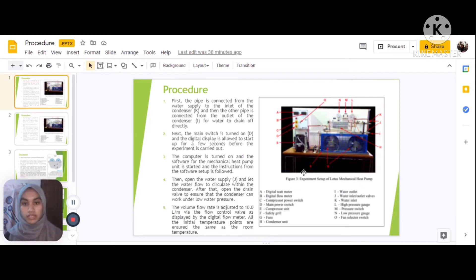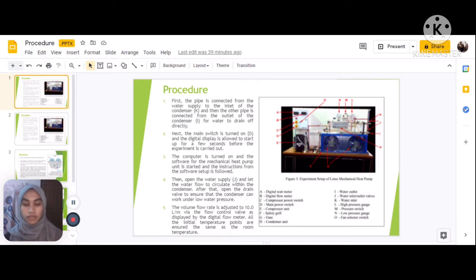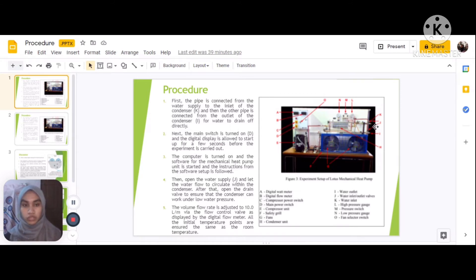Third, the computer is turned on and the software for the mechanical heat pump unit is started, following the setup instructions. Then, open the water supply J and let the water circulate within the condenser. Open the drain valve to ensure the condenser works well under low water pressure. The volume flow rate is adjusted to 10 liters per minute via the flow control valve as displayed by the digital flow meter, and all initial temperature points are ensured to be at room temperature.